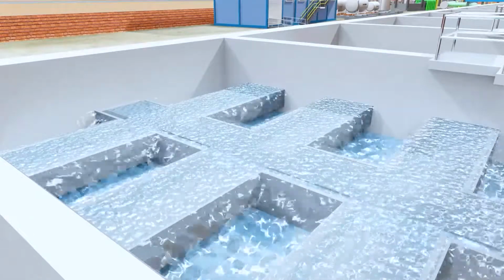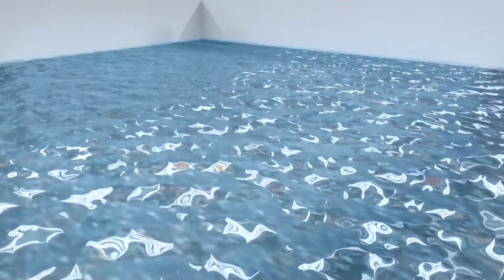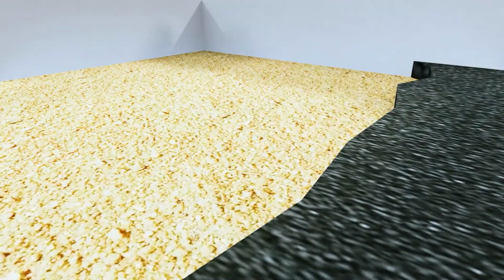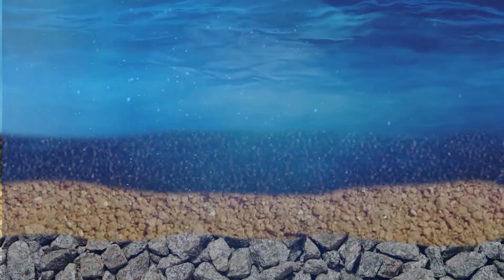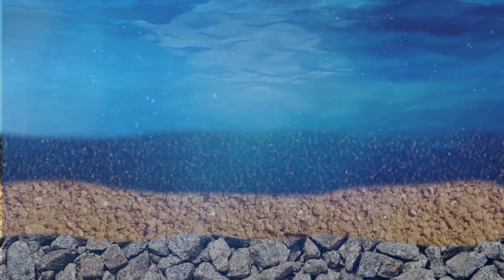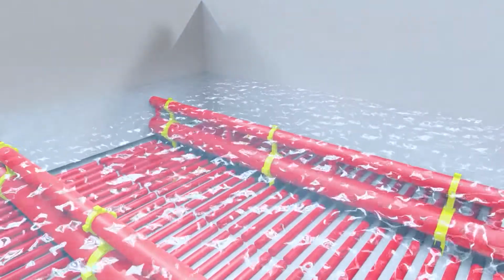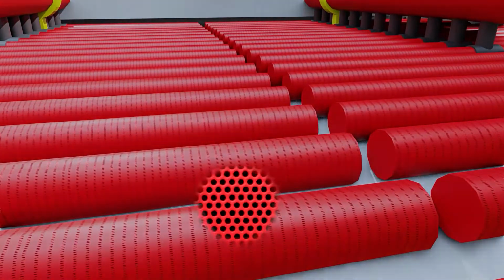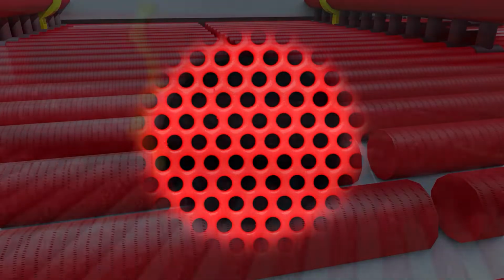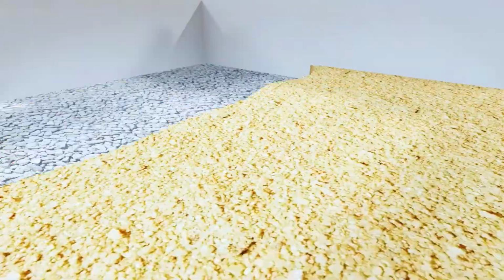Now, the water will flow from multiple media like anthracite, sand and gravel, where natural filtration will occur and impurities will be absorbed by the filter media and same will be removed by backwash. Below filtration medias, there are two outlet headers attached with PVC perforated laterals with 400 micron holes in it. Through laterals, filtered water will be moved out from the filtered water outlet header.